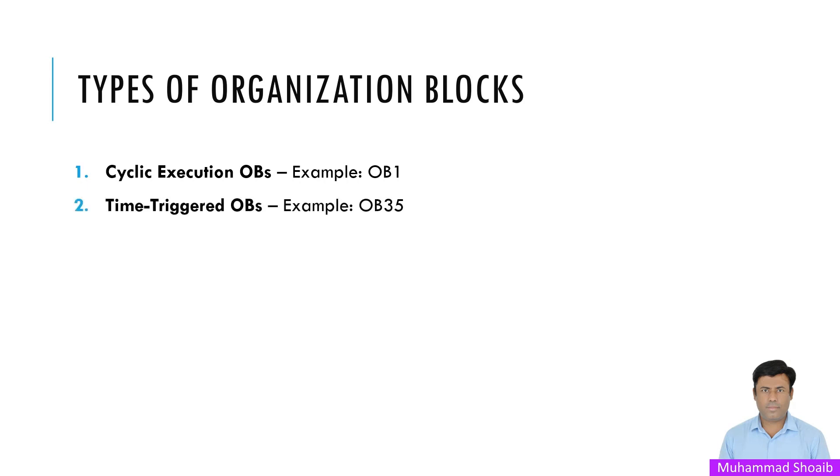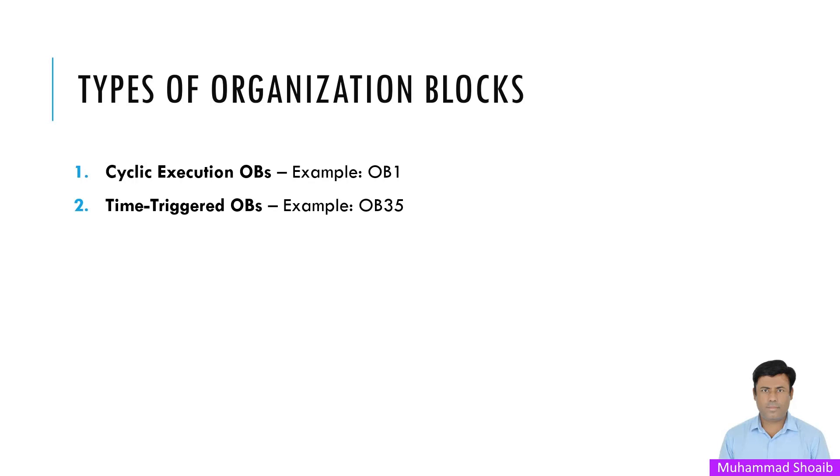So second organization is a time-triggered OBs, for example OB35. Time-triggered OBs like OB35 execute logic at regular intervals. Here we have OB35 set to 100 milliseconds. So there are different types of OBs also that can execute at different time intervals. These are useful for things like periodic data logging or checking sensor status at precise intervals.